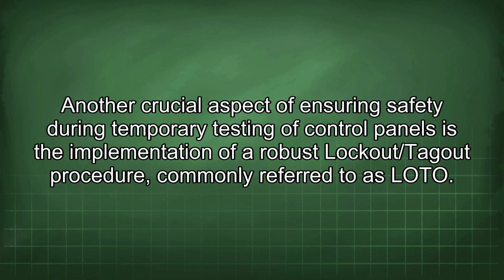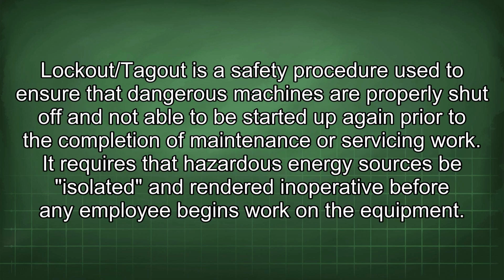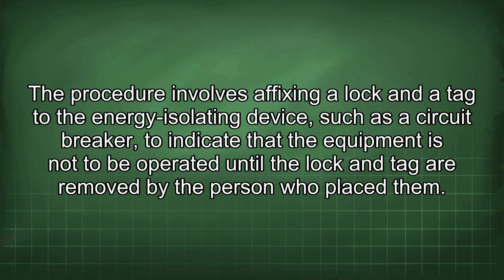Another crucial aspect of ensuring safety during temporary testing of control panels is the implementation of a robust lockout/tagout procedure, commonly referred to as LOTO. Lockout/tagout is a safety procedure used to ensure that dangerous machines are properly shut off and not able to be started up again prior to the completion of maintenance or servicing work. It requires that hazardous energy sources be isolated and rendered inoperative before any employee begins work on the equipment. The procedure involves affixing a lock and a tag to the energy isolating device, such as a circuit breaker, to indicate that the equipment is not to be operated until the lock and tag are removed by the person who placed them.